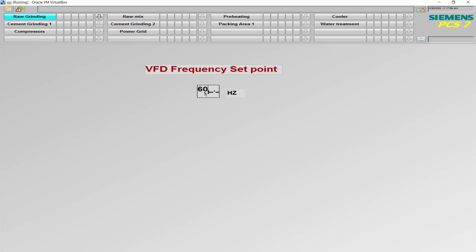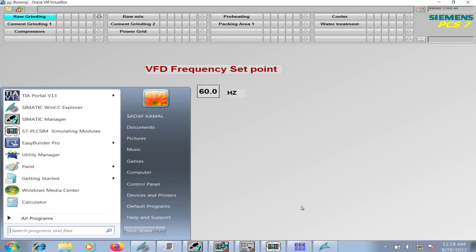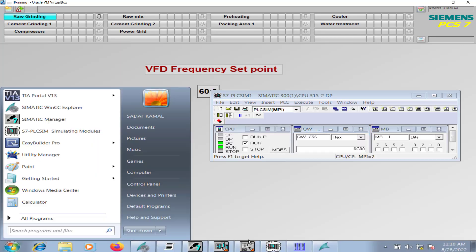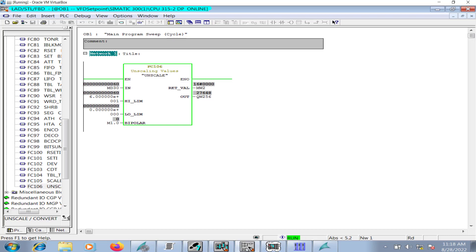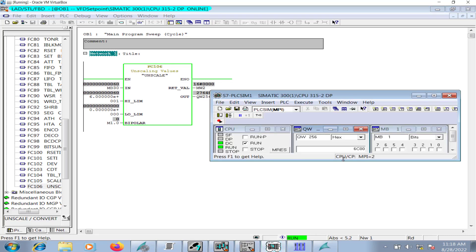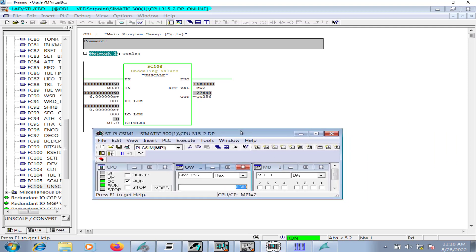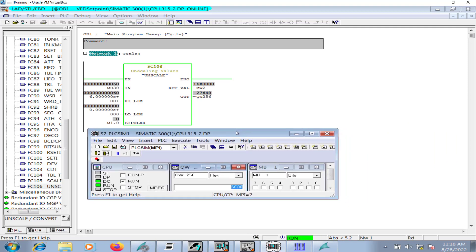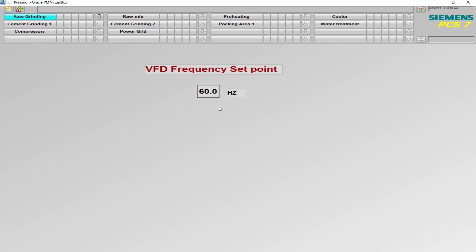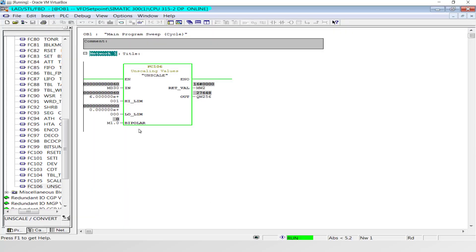If I check it in the simulator, you can see 6 C 0 0, that's the maximum output value of the analog output card and that corresponds to 20 milliampere. So this is how the operator console is used for entering the set point of the variable frequency drive. This IO field is linked with MD 30 over here in the logic, and the value is unscaled accordingly.